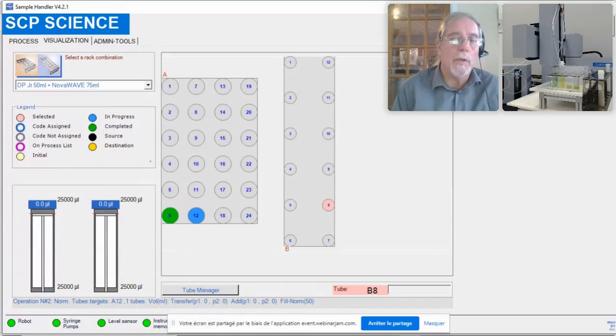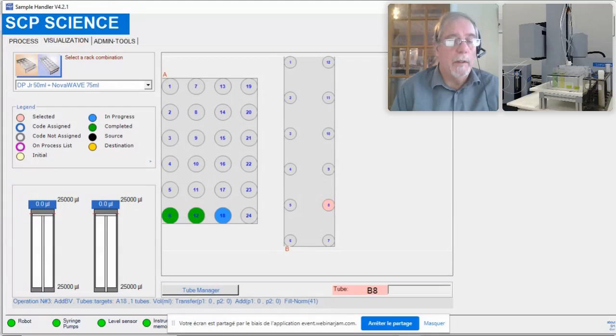So now we can see that we're doing the second vessel with the addition of AccuNorm. The visualization of the two pumps allows you to see what's happening. The dispensing tips when we're normalizing do not go into the solution, so there's no contamination from sample to sample. It just goes into the top of the tube so that it prevents any splashing out. And typically we're dispensing at 3 mils per second and picking up at a half a mil per second. As you can see, we did that third tube with the bulking pump, and the bulking pump has finished. Now it's dispensing the liquid.